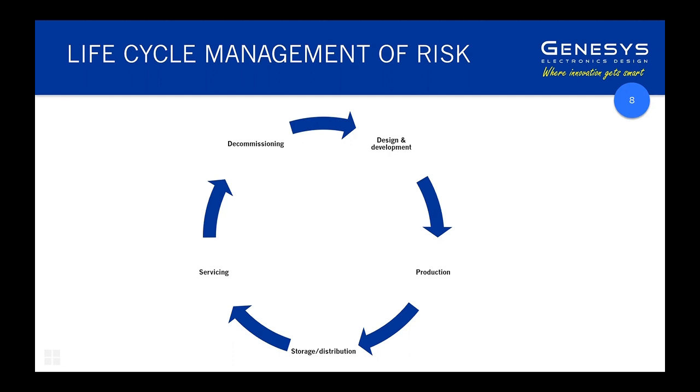Yeah, and just to cap off what Sue said, the presentation today will focus on the failure modes and effects and criticality analysis pathway, other than the HAZOPs and fault tree analysis pathway, which in principle can be used, but I think it's probably fair to say that failure modes and effects analysis is probably the primary one that you'll come across, particularly for electronics and software-based devices, because it just happens to be quite aligned and suitable.